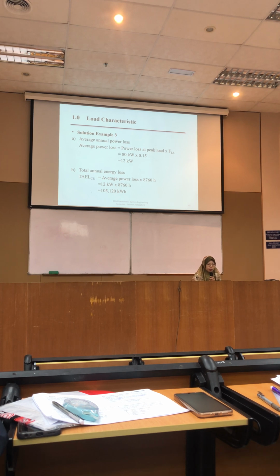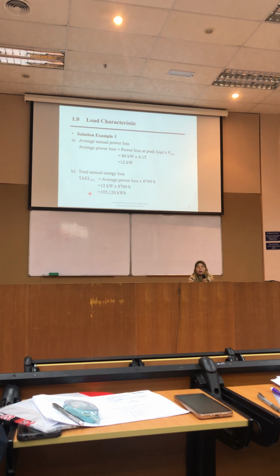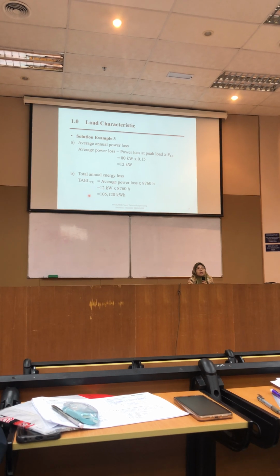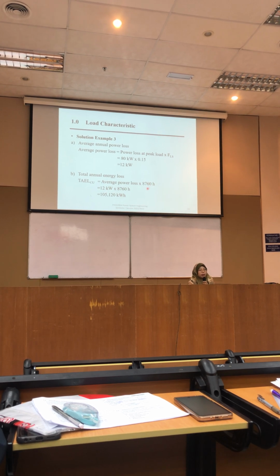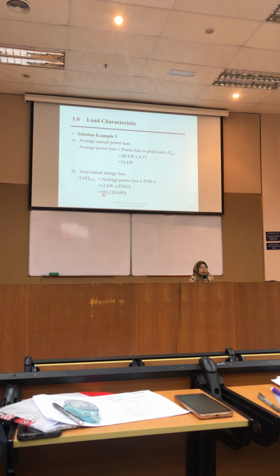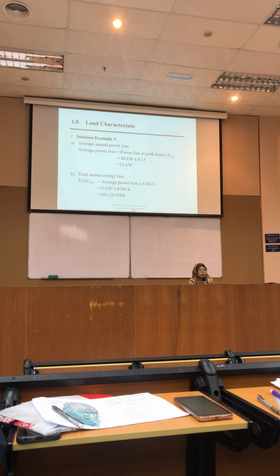The total annual energy loss, how do we get this one here, student? TAEL: total, A is annual, E is energy, L is loss, Cu is copper. We learned from our science or chemistry class that the symbol for copper is Cu. So the average power loss multiplied with the hours in a year gives the total annual energy loss, which is 105,120 kilowatt hour.